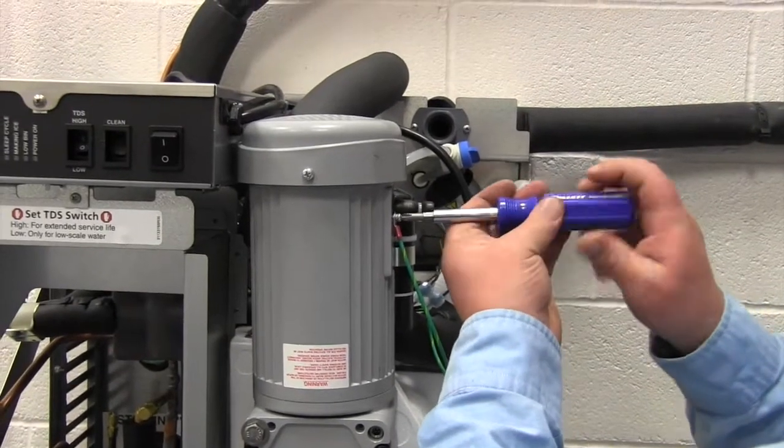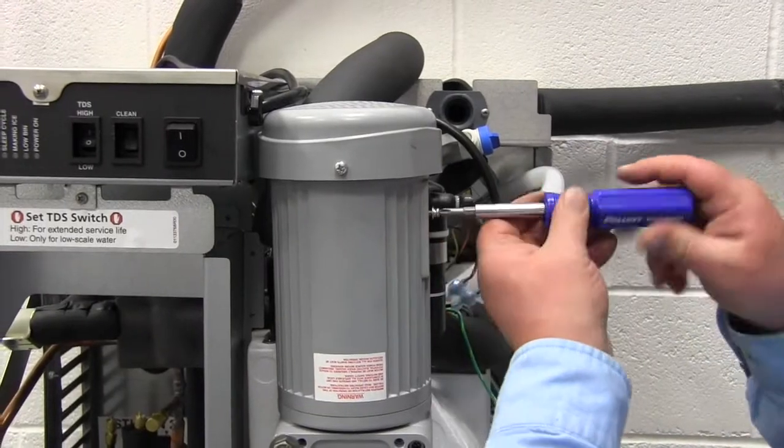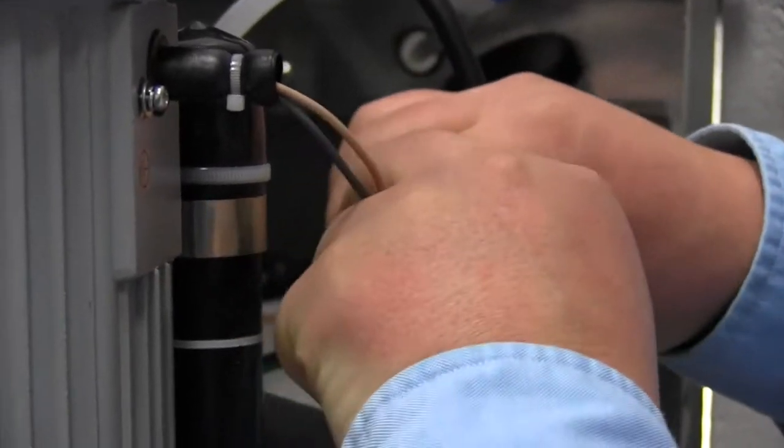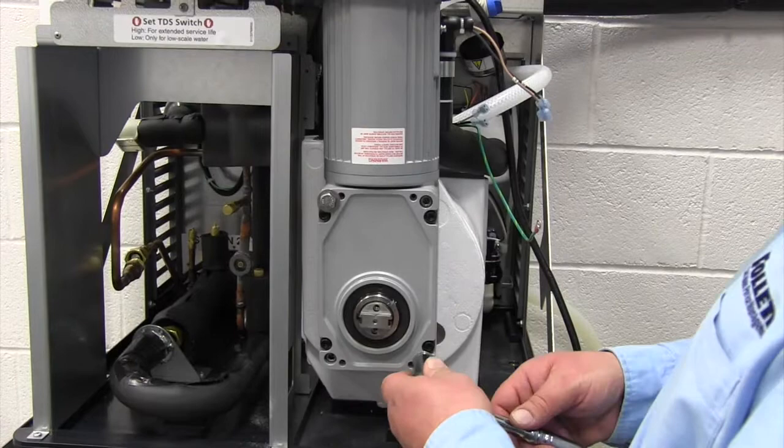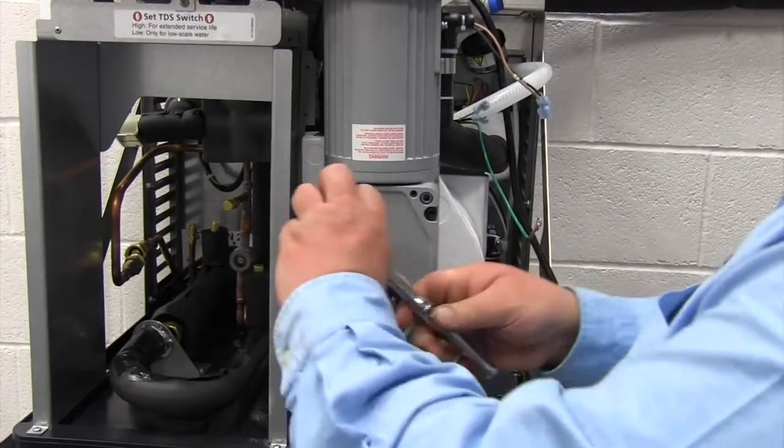Remove the Phillips head screw on the side of the gear motor that holds the ground wire in place. Put the screw back in place so you don't lose it. Now we're disconnecting the two wires that go to the gear motor. We're going to remove the two nine sixteenths hex head bolts that hold the gear motor in place.